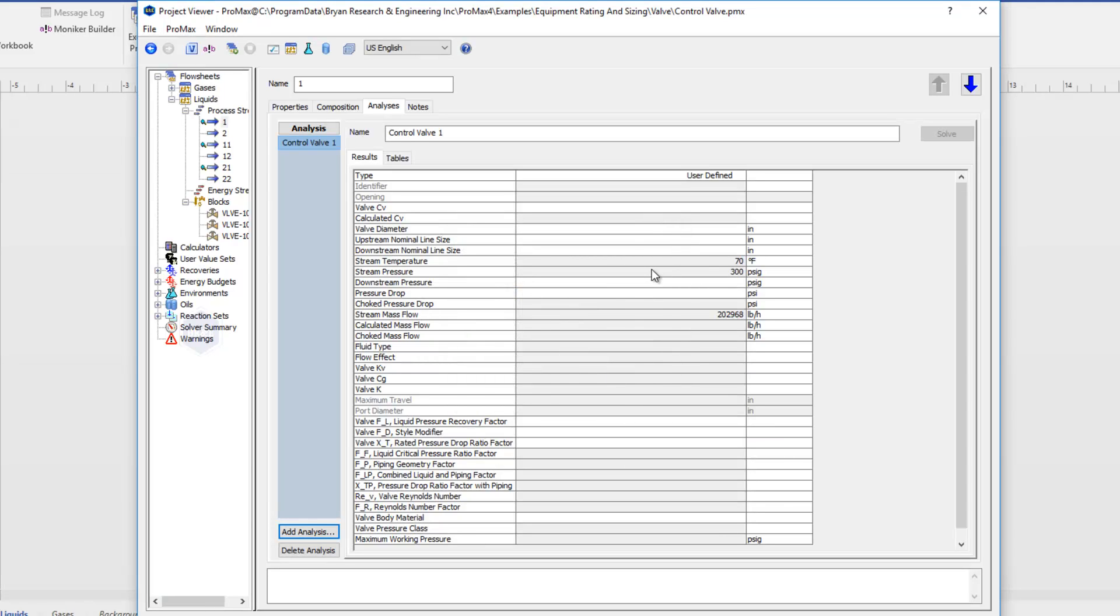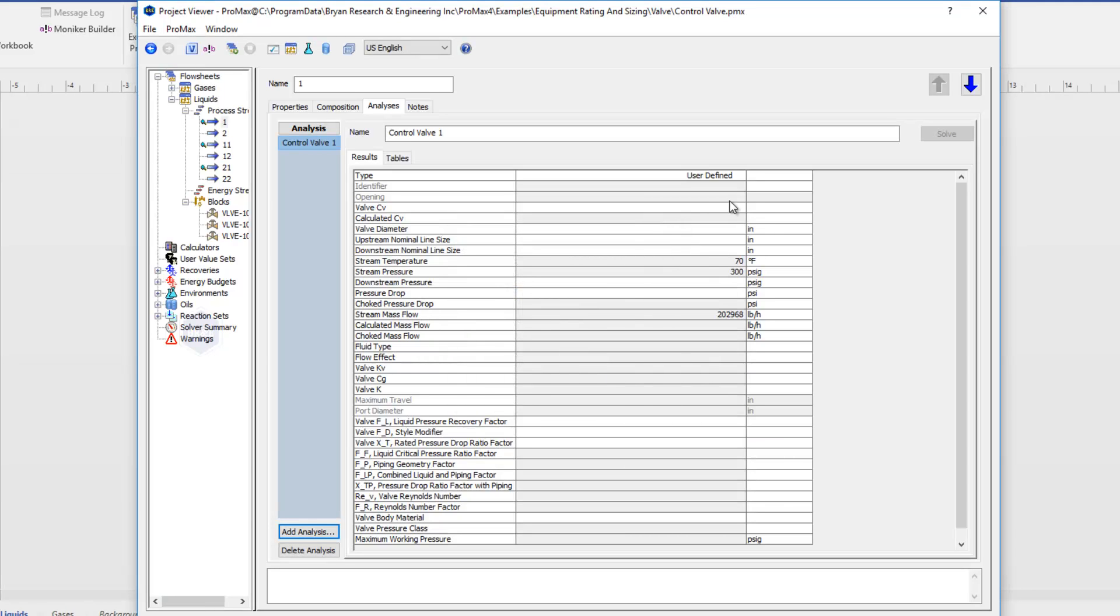So what this is going to do for us, it's going to allow us to define what type of valve we're using. And then we can either give it a valve opening and Promax will calculate what our pressure drop would be, or we can do the reverse and specify a pressure drop and Promax will calculate the valve opening necessary to have that pressure drop.